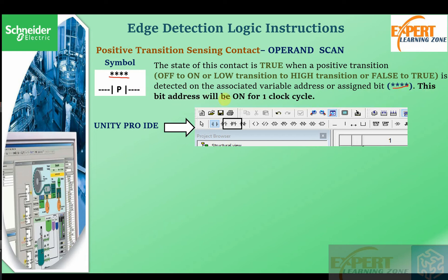This bit address will be on for one clock cycle. It means that if there is a change in the logic on the left side of this contact from low to high transition, then there is a logic one that moves to the right side of the contact for one clock cycle only. In the next clock cycle, if there has been no change, it stays low.